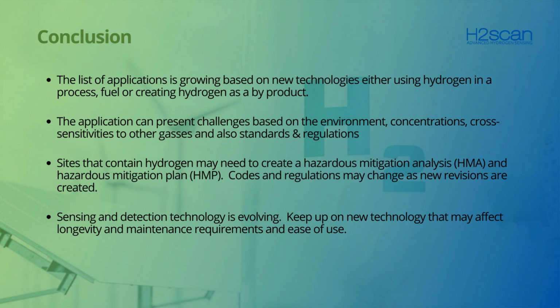So the list of applications is definitely growing based on new technologies, either using hydrogen as a fuel or creating a byproduct of hydrogen or hydrogen used in specific applications for creating other products. The application can present challenges based on the environment, concentrations and cross sensitivities to other gases, and also having to abide by standards and regulations based on industry standards or regulations from authorities having jurisdiction. Sites that contain hydrogen or use hydrogen may need to create a hazardous mitigation analysis, which leads to the hazardous mitigation plan that may be required by your authority having jurisdiction. Review your local regulations and codes in your area for the requirements.